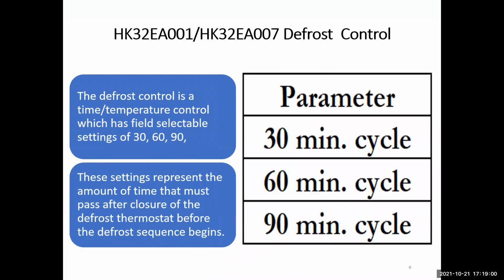The timer is configured to provide a 10-minute defrost cycle, and it's field selectable for defrost intervals of 30, 60, and 90 minutes. The onboard relay switches the reversing valve, the outdoor fan motor, and the auxiliary heat. The defrost termination is provided by a Klixon disc thermostat. The timers are reset by the defrost termination and start when the disc thermostat closes.